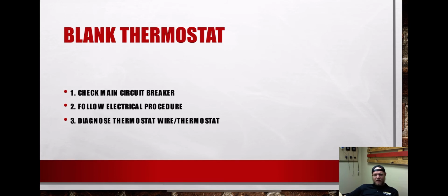So blank thermostat. Obviously, when you're inside the store, you want to check your main circuit breaker. When you checked in with the store, you want to go in there and check that circuit breaker. If it is popped, you do not just want to go ahead and reset it. It's not a hairdryer at your mom's house. It didn't just pop because everything was overloaded. We don't know why it popped right now. We don't know why it tripped. So what you do in that situation is just go ahead and you can either just leave it tripped or just turn it off completely.